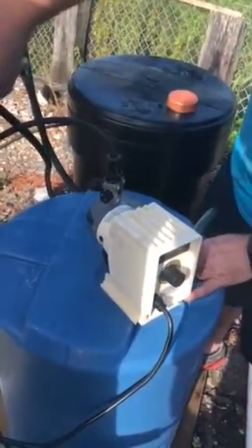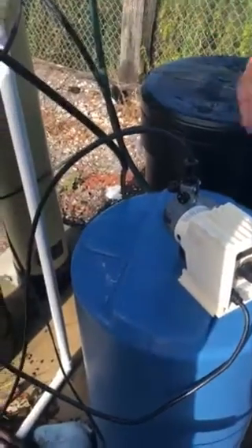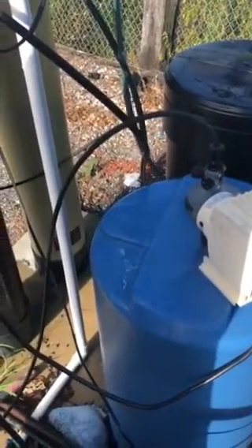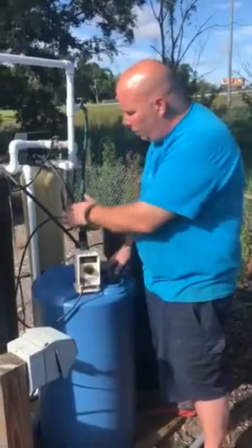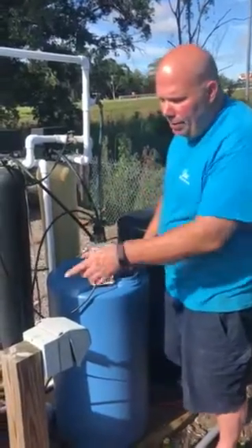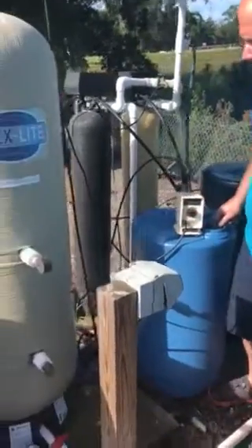Now you'll see this line — it's jumping. My saying is: if the line's not jumping, it's not pumping. Those are the simple ways to prime your pump. Now, if this line's not pumping, that means your injector down here is clogged. We usually have two ball valves, and you can turn it off, take it out, and make sure it's not clogged.